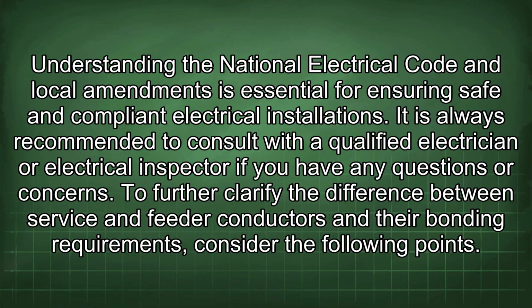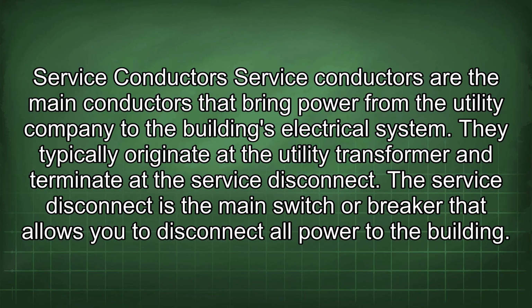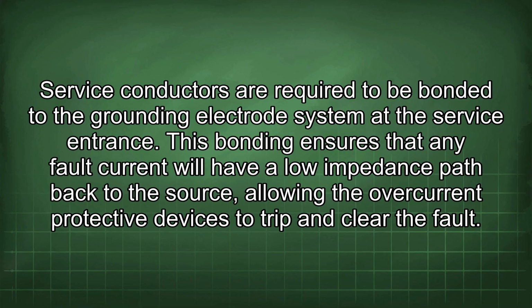To further clarify the difference between service and feeder conductors and their bonding requirements, consider the following points. Service conductors. Service conductors are the main conductors that bring power from the utility company to the building's electrical system. They typically originate at the utility transformer and terminate at the service disconnect. The service disconnect is the main switch or breaker that allows you to disconnect all power to the building. Service conductors are required to be bonded to the grounding electrode system at the service entrance. This bonding ensures that any fault current will have a low impedance path back to the source, allowing the overcurrent protective devices to trip and clear the fault.